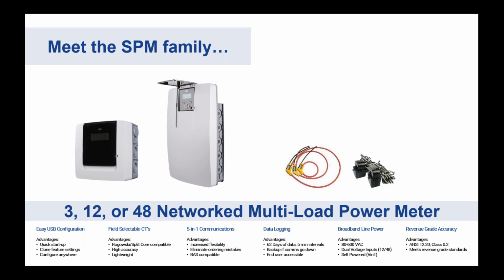To the right of our 2 meters, you'll see our Rogowski coils. We have those in a 12-inch, 24-inch, and a 36-inch length. Rough diameters are 3.5, 7.5, and 11.5 inches in diameter, respectively. These are ideal for odd-shaped cable bundles or bus bar loads, and the 12-inch goes up to 1,500 amps, the 24-inch goes up to 3,000 amps, and the 36 up to 6,000 amps.